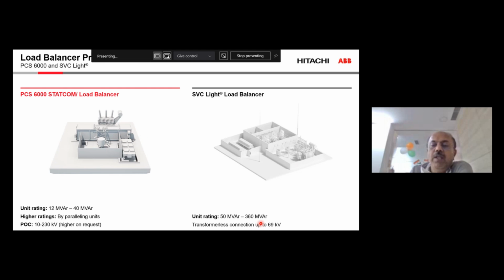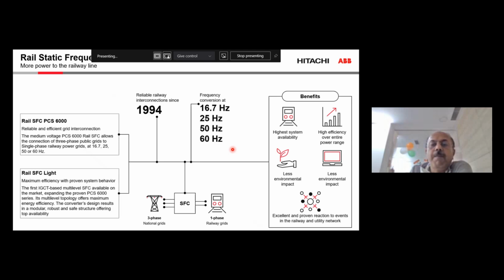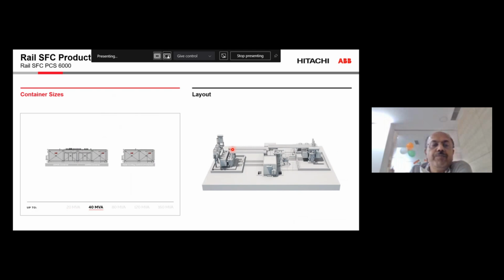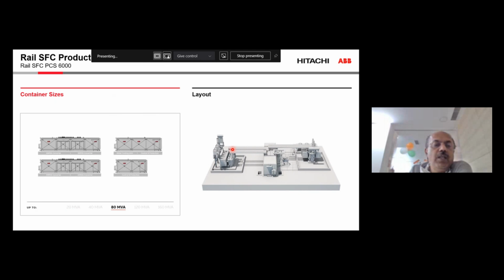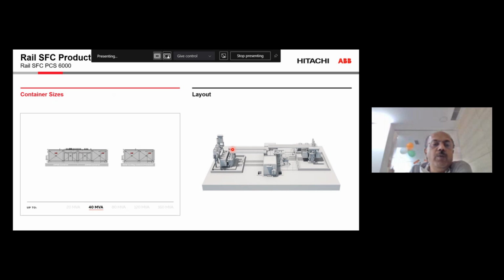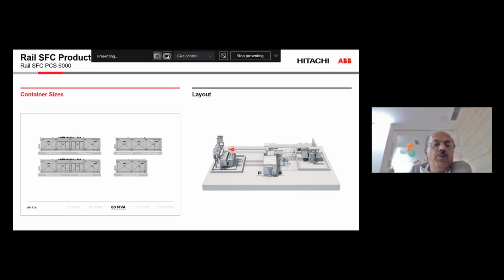And capacity-wise, we have ratings up to 360 MVAR. Maybe a 200 to 300 kilometer corridor can be entirely compensated by having one or two load balancers located in one station, or at the two ends of the substations. So we can add any number of stations. That is what is indicated here: say 20 MVA, 40 MVA, 2 stations, and then 80 MVA if you want to have that location. So it is very modular in nature, and it is totally suitable for the outdoor environment. We don't need much space, and it can be located anywhere on the corridor network, feeding the entire corridor basically.